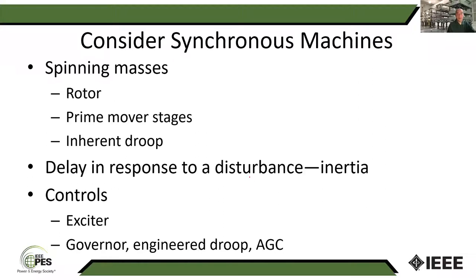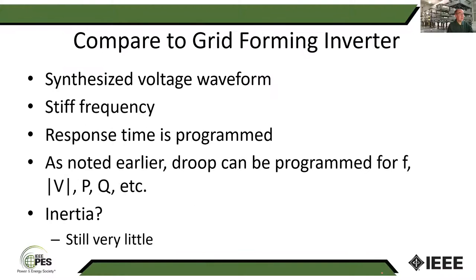The first step you see to that slowing down is the change of its phase angle. And so there's some inherent droop, and then usually the governor will have some added droop, or controlled droop, put into it. And then there's also inertia because of that energy stored in it. And so you have controls: you have an exciter, you have a governor with an engineered droop, you may have a local automatic generation control that's tied to a centralized one.